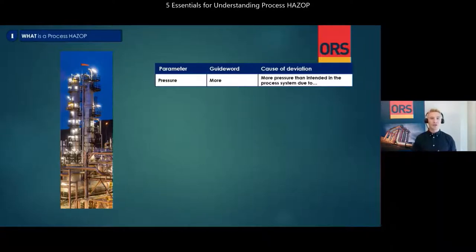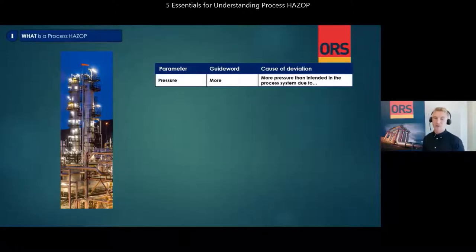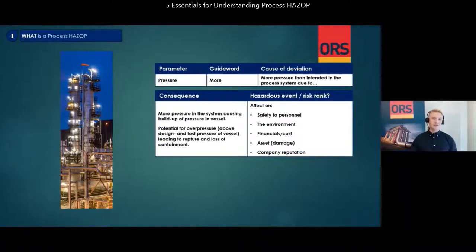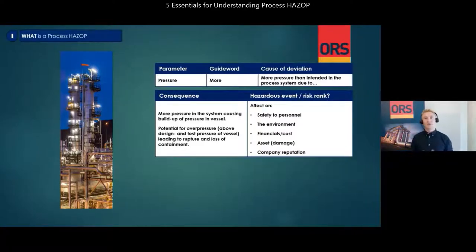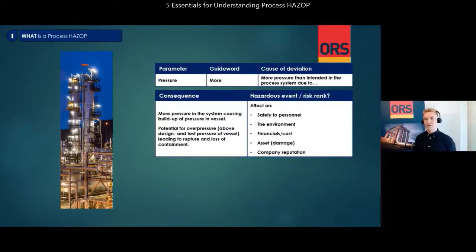If a cause for more pressure is identified, the consequence is defined excluding all existing safeguards. The level of detail of the consequence, such as quantification of what pressures one might experience, depends on three things: the requirements from the company, the time available in the workshop, and information available. Continuing on our example, we have the consequence: more pressure in the system causing buildup of pressure in vessel, potential for overpressure above the design and test pressure of the vessel, leading to rupture and loss of containment.